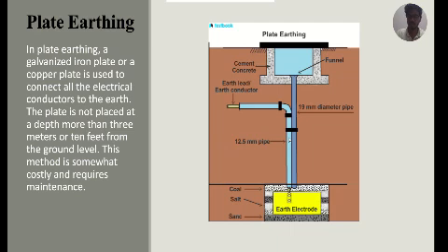This method provides a large surface area for grounding, making it effective in dissipating electrical surges. However, it requires regular checks for corrosion over time. Plate earthing is commonly used in power stations, industrial plants and other large electrical installations. This method is somewhat costly and requires more maintenance as compared to pipe earthing.